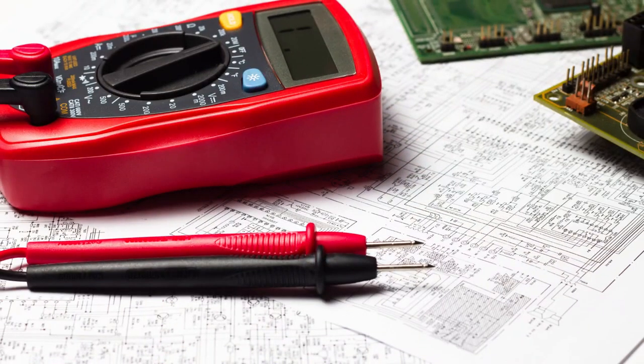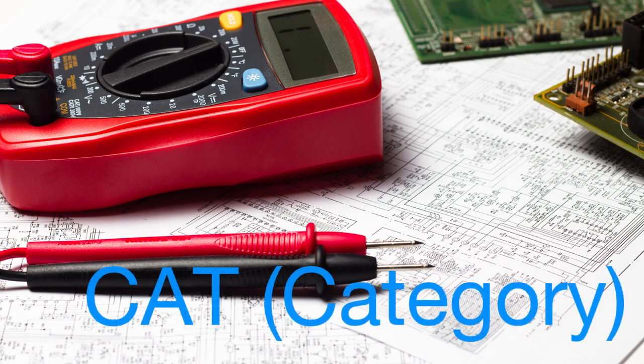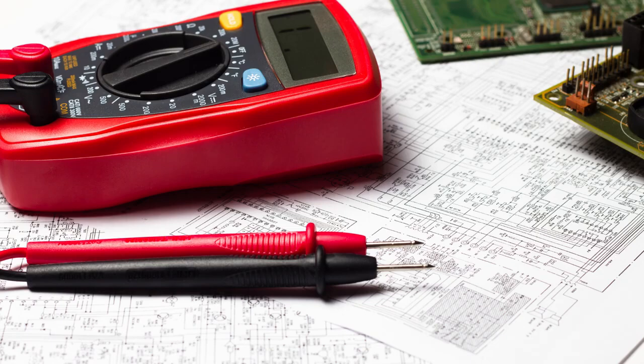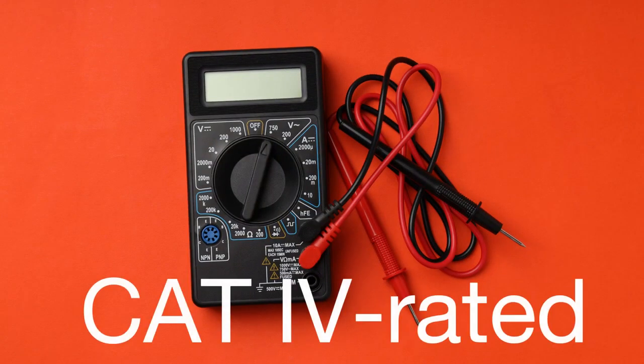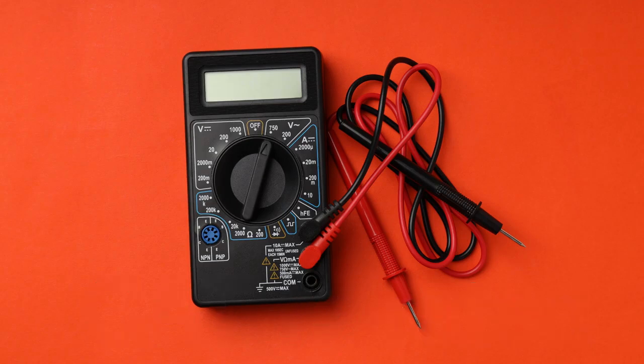Moreover, many digital multimeters are equipped with safety ratings, such as CAT category ratings, indicating their suitability for different voltage levels and environments. For instance, a CAT 4-rated multimeter is safe for testing in areas close to the utility connection, like outdoor wiring or industrial environments.